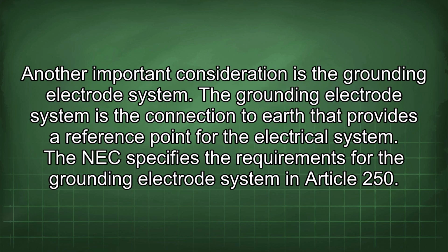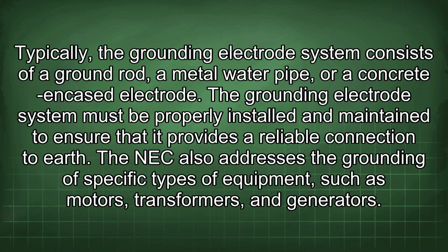Another important consideration is the grounding electrode system. The grounding electrode system is the connection to earth that provides a reference point for the electrical system. The NEC specifies the requirements for the grounding electrode system in Article 250. Typically, the grounding electrode system consists of a ground rod, a metal water pipe, or a concrete encased electrode. The grounding electrode system must be properly installed and maintained to ensure that it provides a reliable connection to earth.